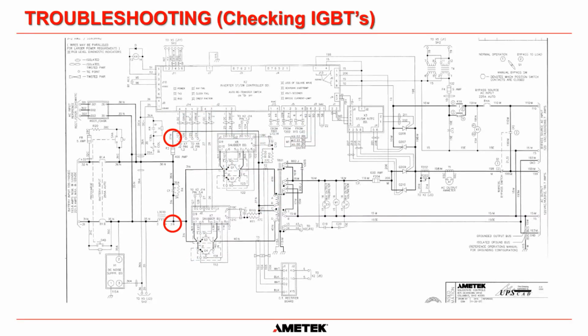And by checking at this point here and at this point here, you're actually checking both sets of IGBTs, because if you do get 0 ohms, then that must mean there is a short either that way to that point there, or a short that way to that point there. So if you find your Fluke reads anywhere from 0 to 4 ohms really, then there is an IGBT that has shorted. And then what you need to do is disconnect the power cables from the IGBT itself inside the system, and then test them again to find out, is it this one or is it this one?